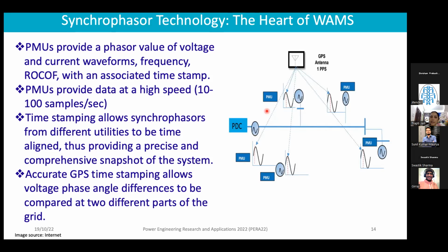These are all associated with a timestamp that is synchronized with GPS, so all measurements are taken at the same timestamp, giving you a very clear snapshot of the whole grid. They also provide data at a very high speed, varying from 10 to 100 samples per second.